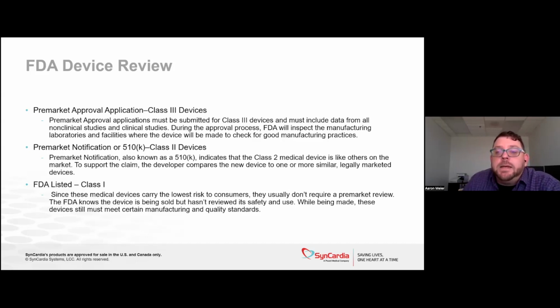You don't necessarily need to do a large-scale clinical trial to demonstrate the equivalence of a Class 2, but for Class 3s, you have to get out there and demonstrate in a patient, in its use environment, it is going to meet those goals. And so that's really the much bigger hurdle that comes with those Class 3 devices. Does that make sense?